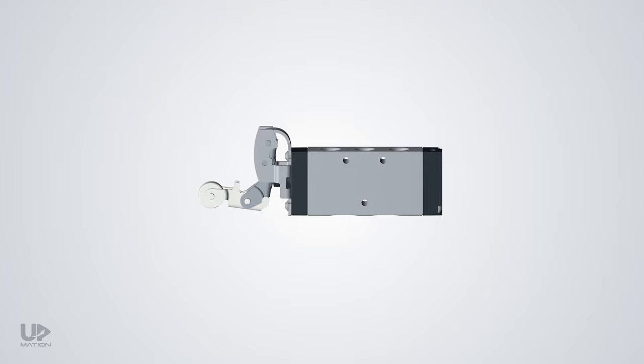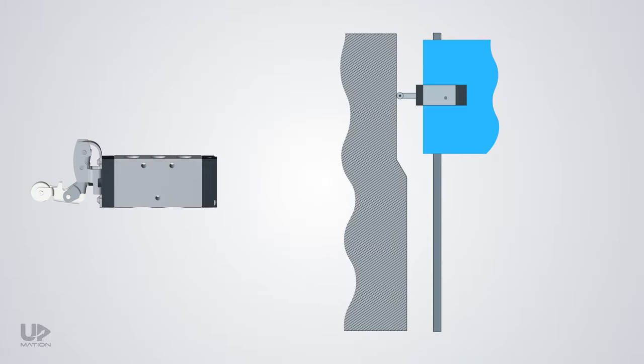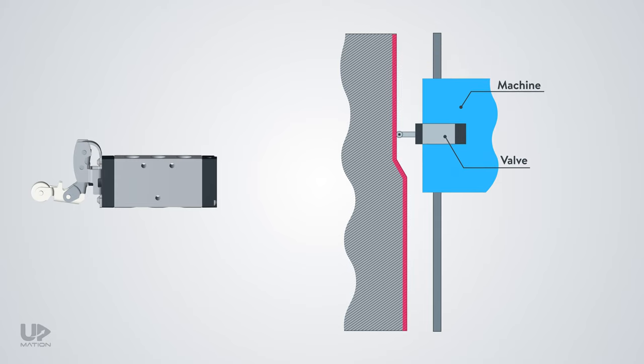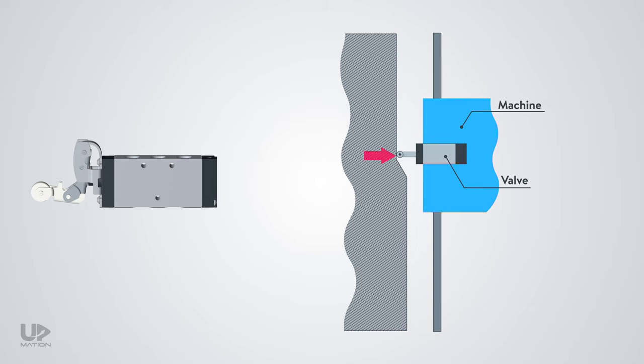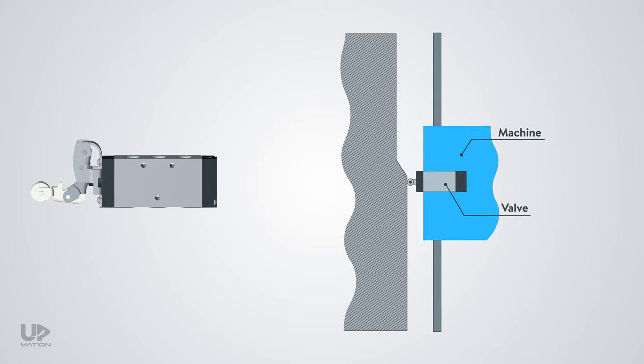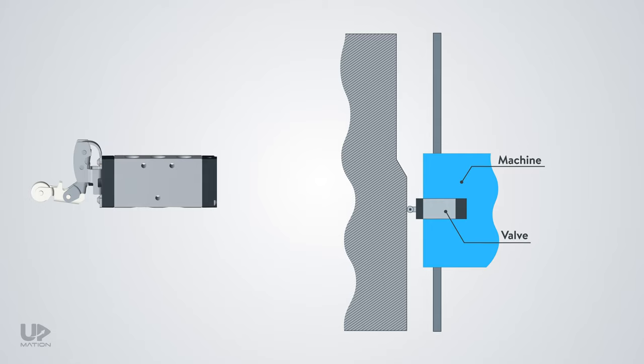An example of a mechanically actuated DCV is a roller operated directional control valve or cam operated directional control valve. For instance, the valve is fixed on a machine and as the machine moves, the roller senses an adjacent surface. In a particular position, it will operate the valve and move the spool to the other side.